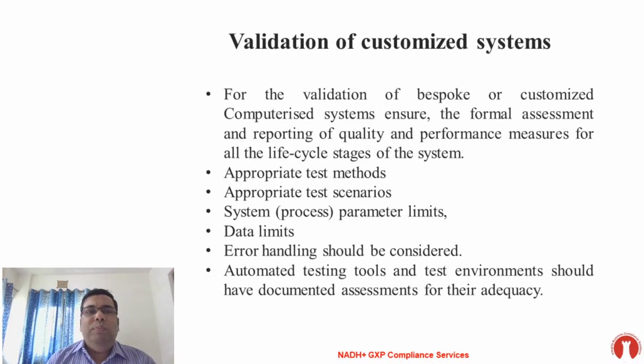For the validation of bespoke or customized computer systems, the formal assessment and reporting of quality and performance measures for the life cycle stages of the system, appropriate test methods, appropriate test scenario, system parameter limits, data limits, error handling, automated testing tools, and test environment should be considered.